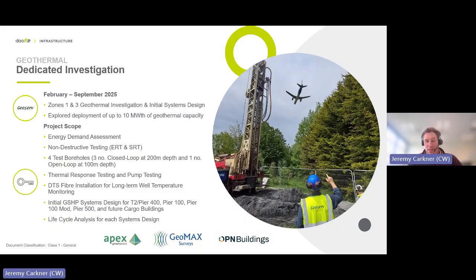That fiber installation is really to help give an indication of long-term temperatures. We've done a couple of readings since the original installation to validate that the ground temperatures are stable. I think they're about 12 degrees Celsius in the borehole we've measured so far. We haven't been able to measure them all, because some of the boreholes are in quite field-like areas where there's been a lot of rain this year, so we've been waiting for those readings until drier weather.